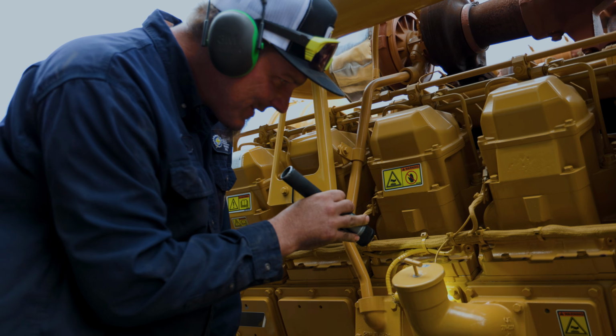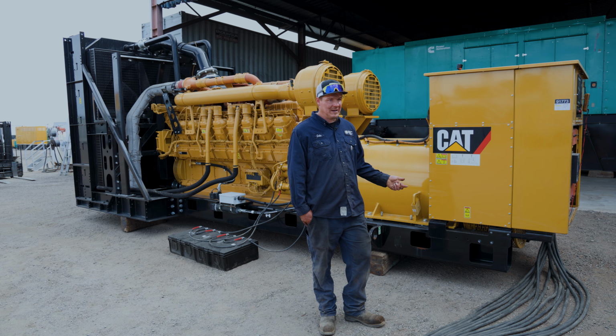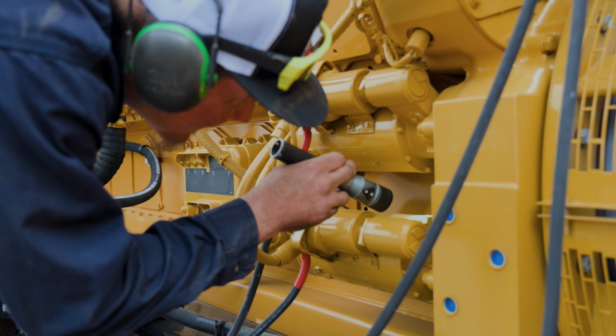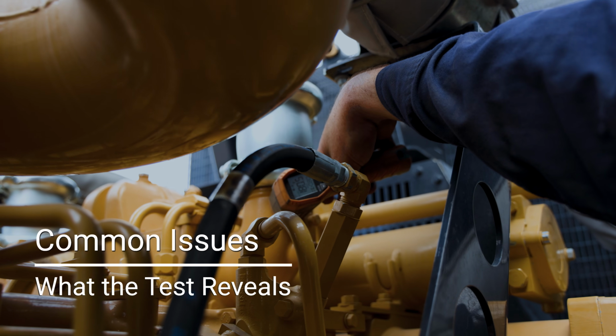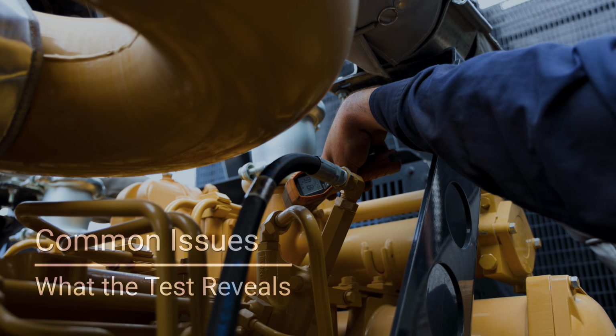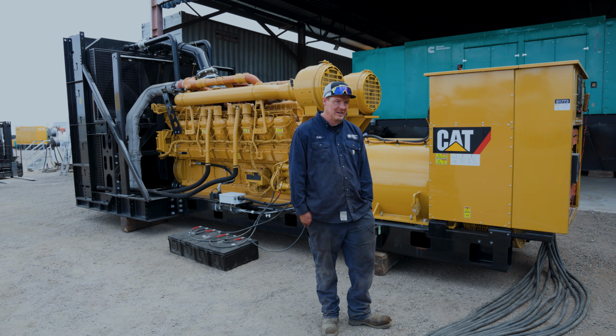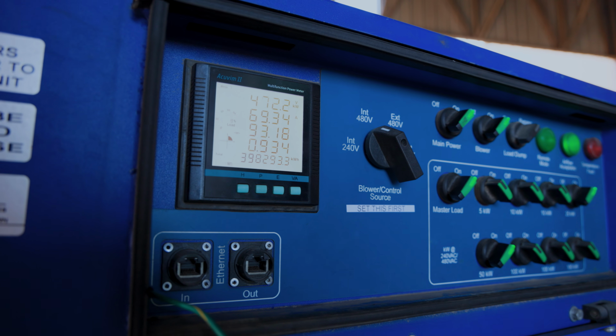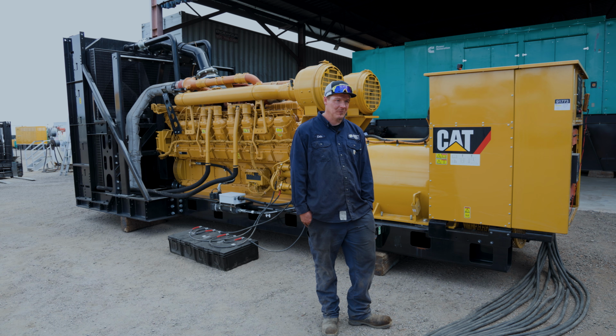I'm making sure the temperature is not climbing, and if it is, then we're going to diagnose and fix what the problem is. Common reasons that I've seen: overheating issues, radiators leaking, bad thermostats, voltage is unstable. So that's a good sign that something could be going on with the regulator. The control panel reading the incorrect voltage or amperage.